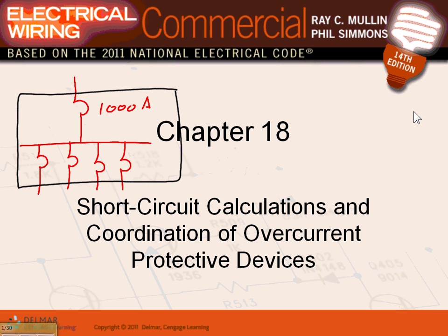Number one is interrupting rating. I'm going to put this one, number one, with blue. Right here for the circuit breaker, interrupting rating for short circuit. Let's call it short circuit interrupting rating. This one I'm going to put at 85,000 amp. So this is a 1000 amp circuit breaker that interrupts up to and including 85,000 amp, right? That's how much this big boy can handle.